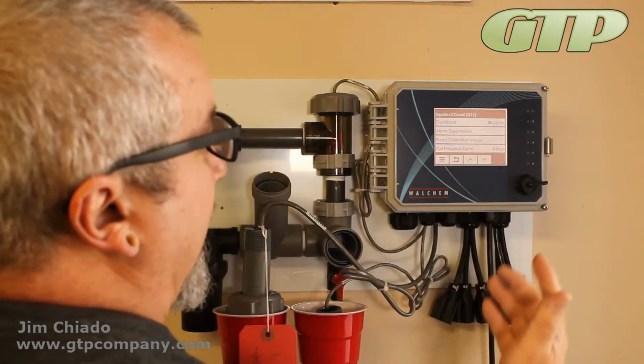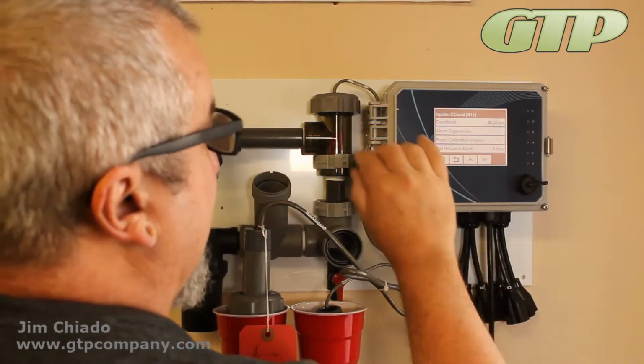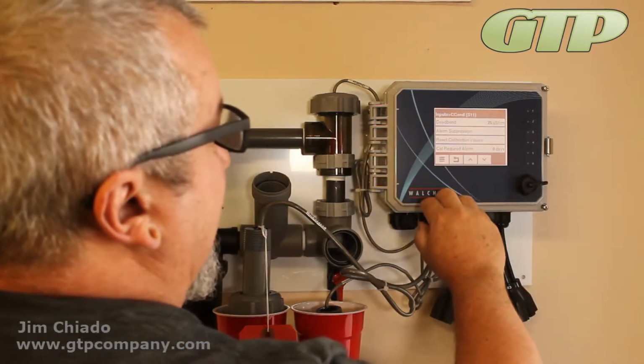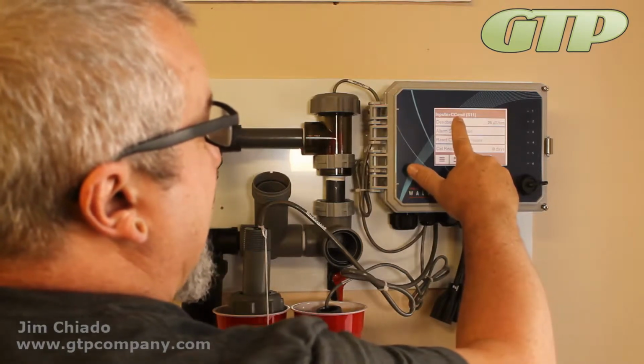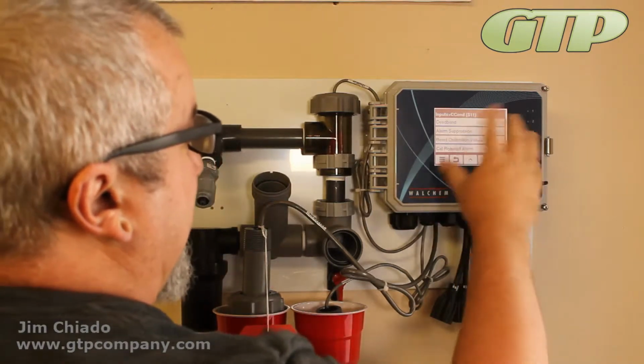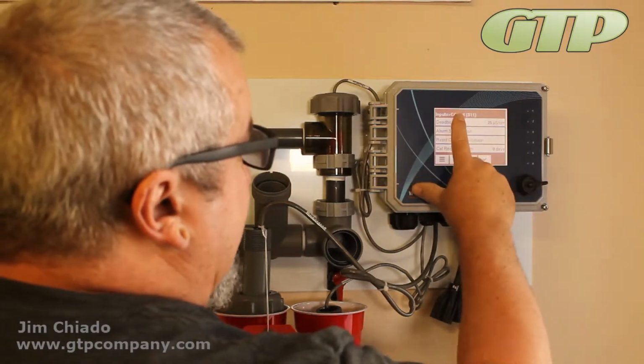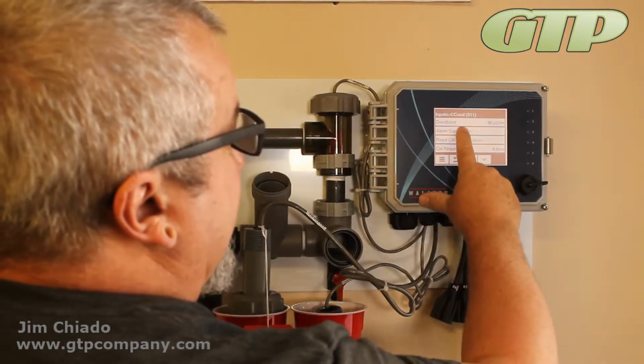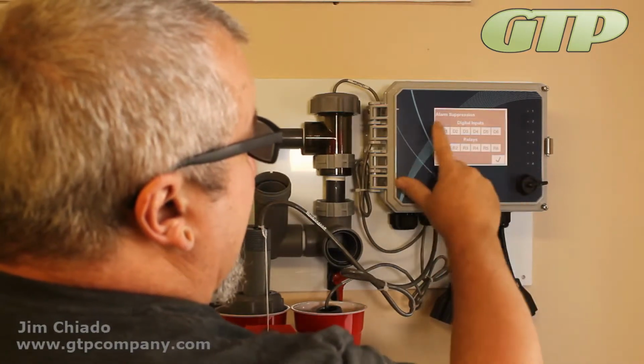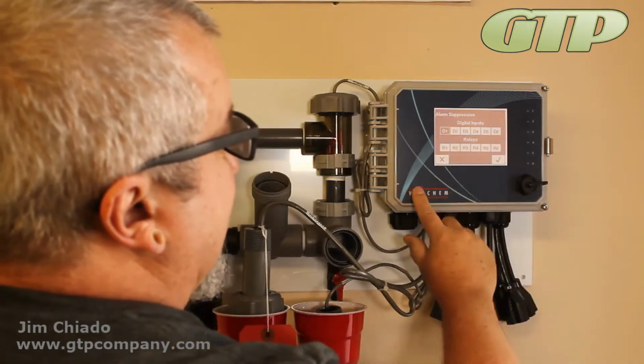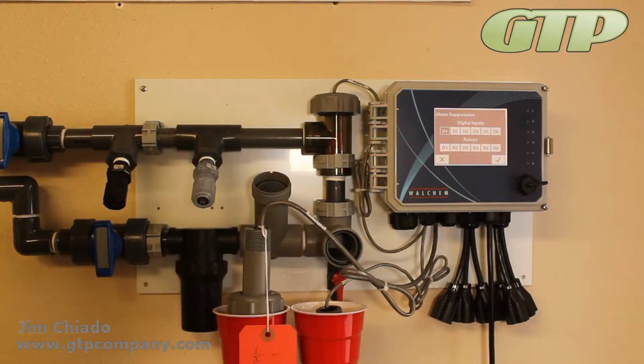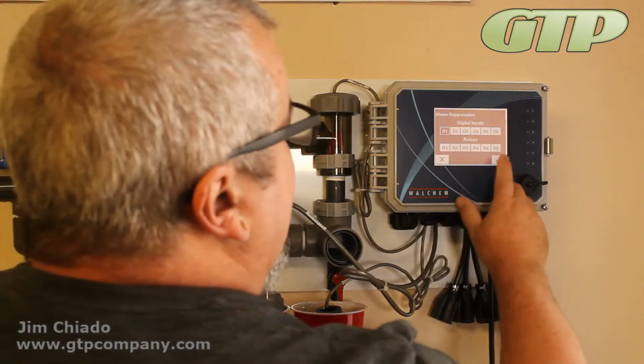Okay, high alarm, low alarm, not necessarily as much. Definitely middle of the road there. Deadband: this deadband on the conductivity input is when you want it to shut back off. It's only based on the alarms. Alarm suppression: if you have the alarms suppressed when D1 is active, that's good, because maybe it's bailed out or it's drained the line or whatever you have it set up.